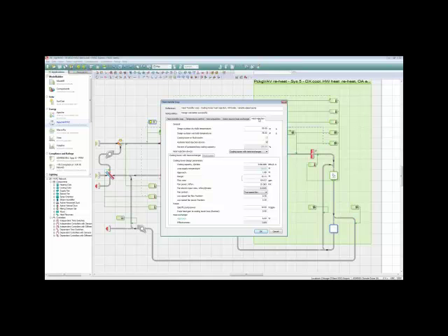And so therefore, there's no way for this device to cool that fluid in an economizer mode before it gets to that heat pump device. So the heat pump, which is equivalent to a lot of small chillers out in the zone level, are just dumping heat on the heat transfer loop.